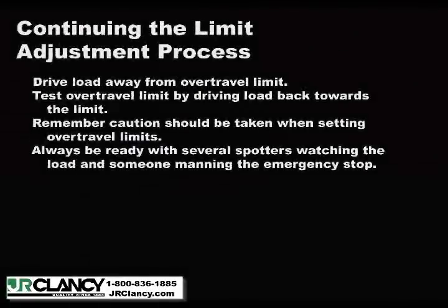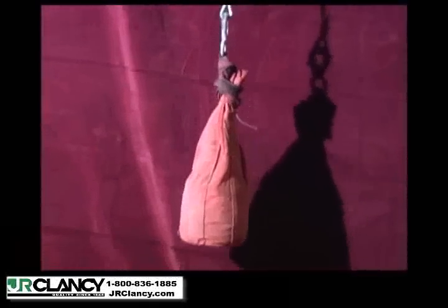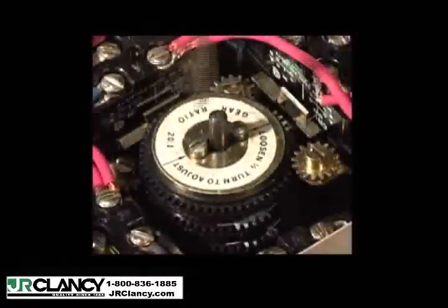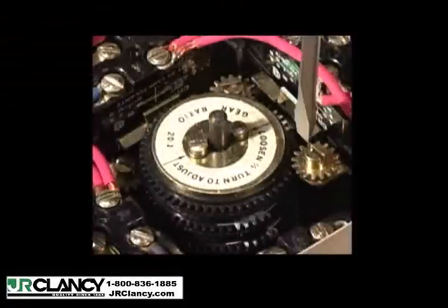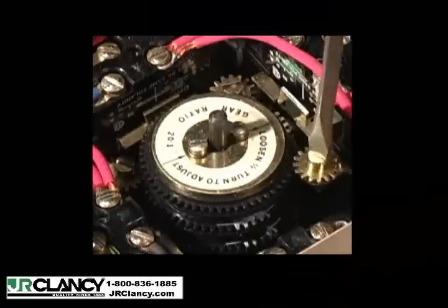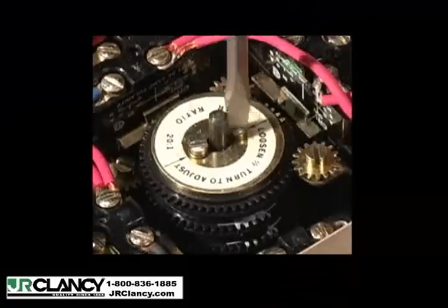Continue by driving the load away from the limit that was just set, then test the limit setting by driving the load back towards the over travel limit. Remember that caution should be taken when setting over travel limits — always be ready with several spotters watching the load and someone manning the emergency stop. In this instance, we have unfortunately set the limit to a position where the load has become misaligned. We must go back and readjust the limit to stop the load just a little sooner.